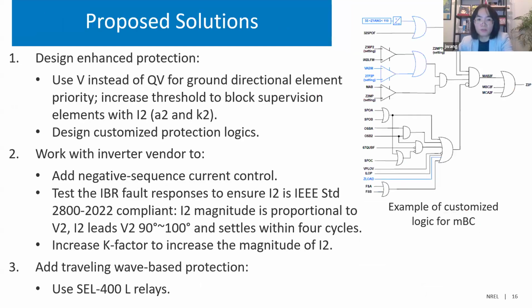And then I will propose the solution to our utility partner as follows. First, we propose enhanced protection. For example, we can use V2 instead of Q/V for ground directional elements priority, and also increase the threshold to block the supervision element that relies on the negative sequence. So this is for the ground fault. For the phase-to-phase fault, we design customized logic as shown here, and we add a voltage supervised element that increases the reliability. And we have tested this enhanced logic. It works pretty reliably. So this is the first solution.